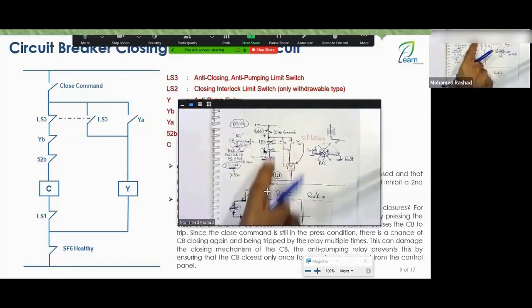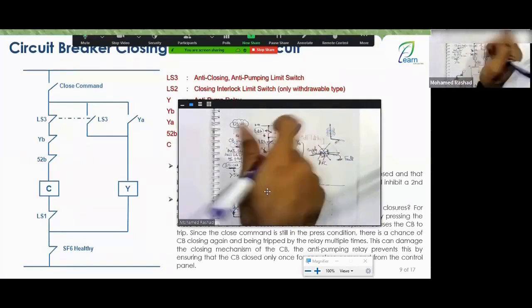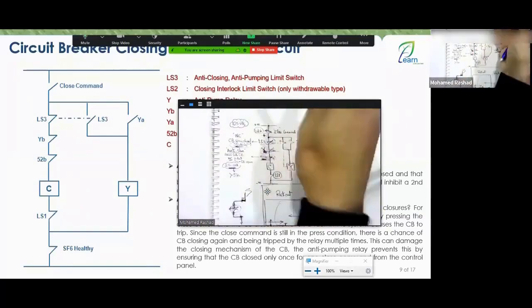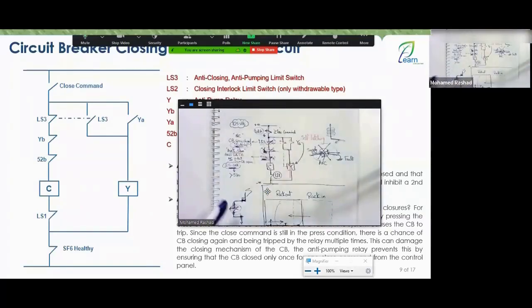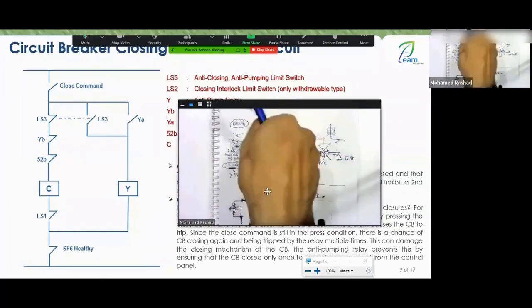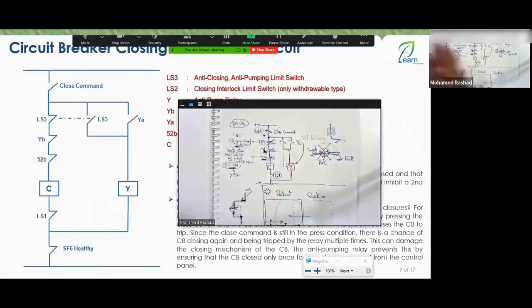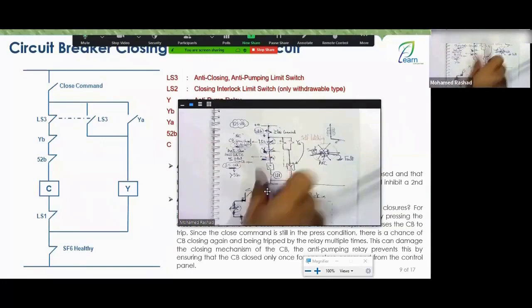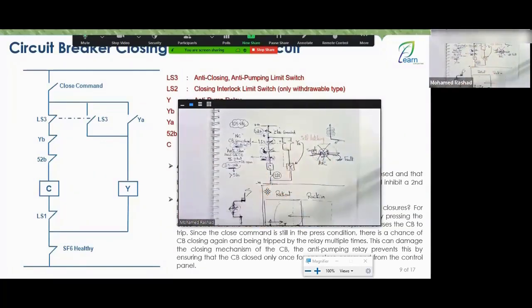Close the breaker. Now, if someone comes and the breaker is in between, or the breaker is not totally racked out, or totally racked in, meaning it hasn't been fully inserted or fully removed, and someone tries to close it without realizing that it's neither totally racked in nor totally racked out, the breaker won't close. They'll keep trying to operate the switch, wondering why it won't close, until it gets stuck and burns out. That's why there's a contact here called a limit switch. What is this limit switch?